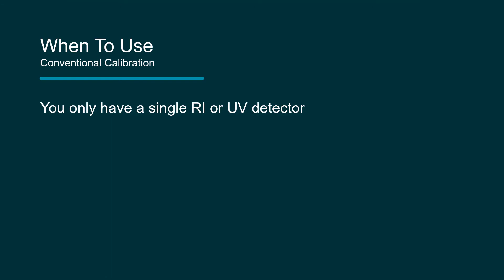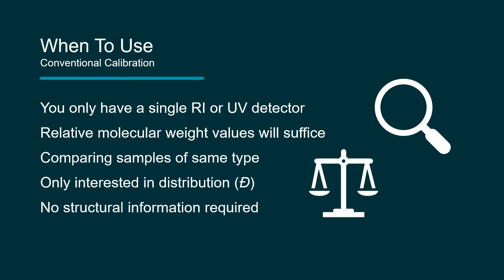While limited in its capabilities, conventional calibration can be a useful analysis method if you only have access to a single concentration detector. It is also valuable if all you need are relative molecular weight values. If you're comparing samples of the same type, only interested in the sample's distribution, have no need for structural information, or are looking for an economical method to analyze your samples, then conventional calibration can work for you.